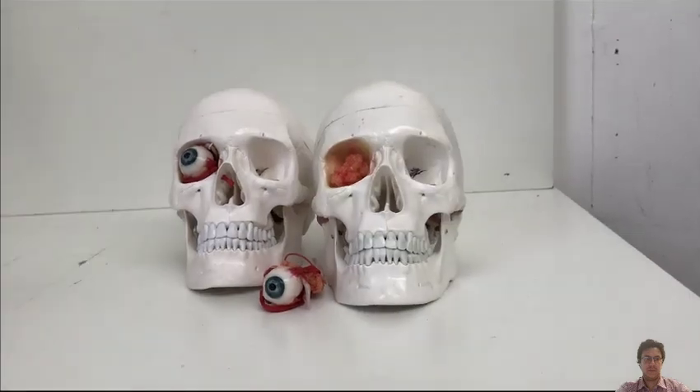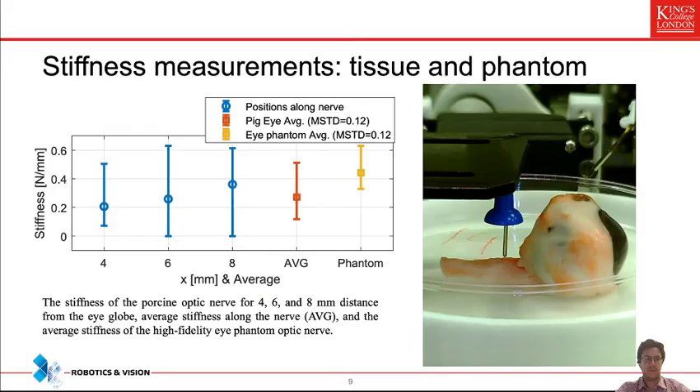Looks are one thing, but conformance with normal biomechanical characteristics of the eye — particularly the stiffness of the optic nerve — is very important. We characterized the phantom properties by measuring optic nerve stiffness on porcine eyes using a blunt needle, recording forces and displacement, and compared this with the stiffness of our phantom. They are more or less in agreement, meaning if we can manipulate and perform an incision in our phantom with regard to its optic nerve, we are performing at least as well as with a porcine eye.